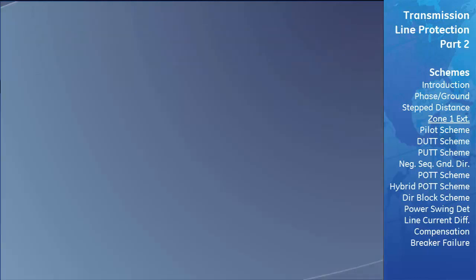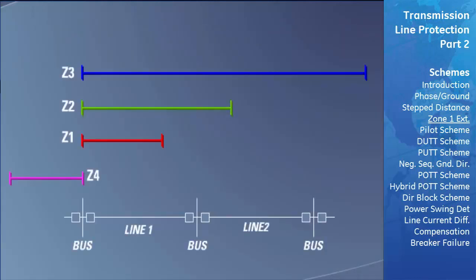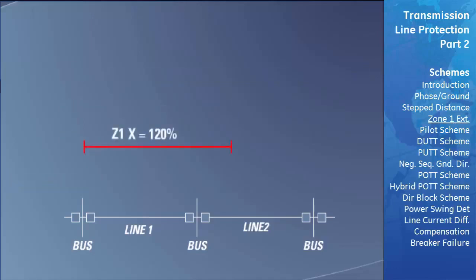The Zone 1 Extension Scheme, like the stepped distance scheme, has four zones of protection. The difference is that an additional Zone 1 impedance setting, labeled Z1X, is set higher to overreach into the next adjacent transmission line—usually set to 120% of the impedance of the entire line, the same as the Zone 2 setting. This extended Zone 1 is used by the distance relay until it detects a fault within its zone, at which point the relay immediately trips the transmission line with no delay, even if the fault is in the adjacent line's area.